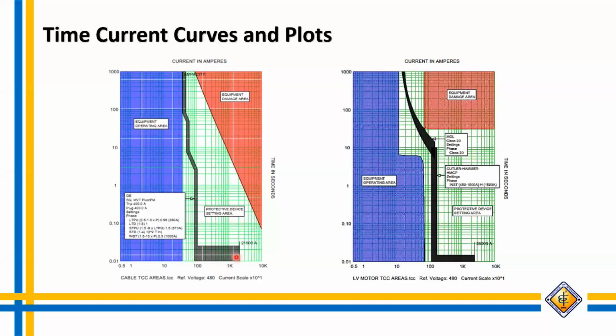So if the circuit breaker is not able to trip in a certain period of time when there is a fault, definitely your damage curves here will be affected. For example, you have cable damage curves here, the transformer. So definitely it will not be protected against the fault current. So this is an example of overload. Okay? Later, I think I have an example here, which I made quickly. And then we also have the MCP, the motor circuit protector.